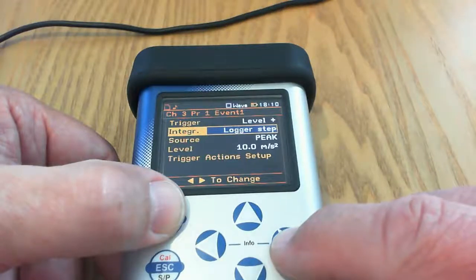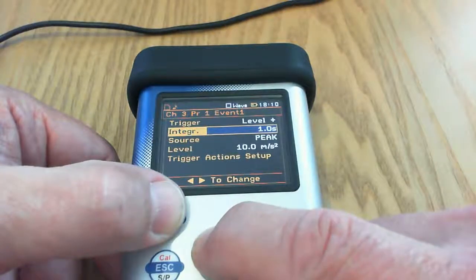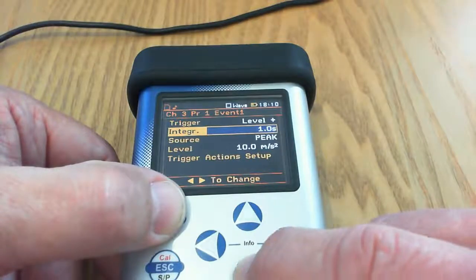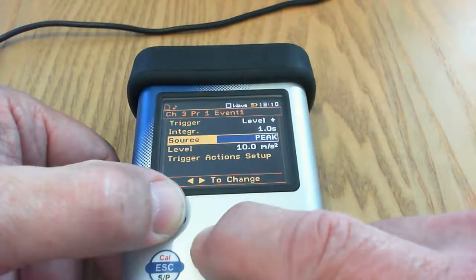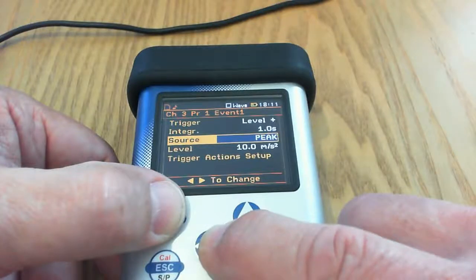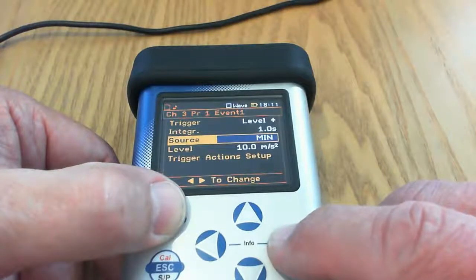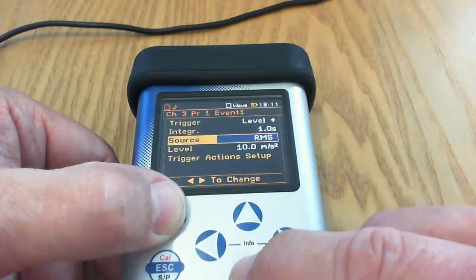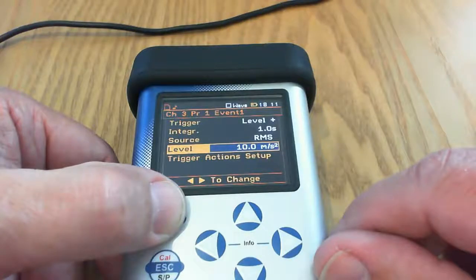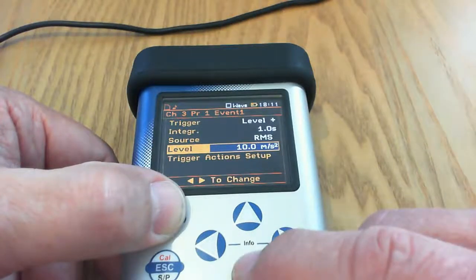You can also choose the integration time for the trigger. For example, if I want to look at if the level goes above a certain threshold with an integration time of one second that will work fine. You can also choose the parameter that you want to trigger off. At the moment it's set to peak. If you're doing peak particle velocity that's fine. If you want to do acceleration for example you might just want to take the simple RMS value. Here you can put in the level that you want to trigger off. In this case if the RMS level with a one second integration time goes above 10 meters per second squared that will give you a positive trigger action.